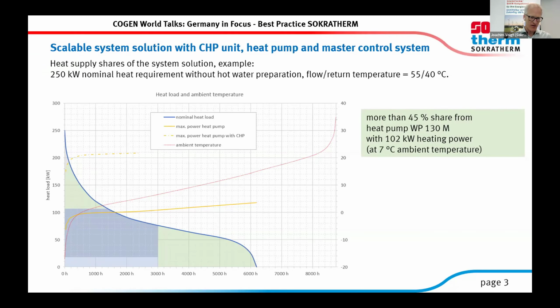As you see in the yellow curve, in the summertime, the heat pump is a bit too big, but this helps in the wintertime to cover more of the peak load demand with a heat pump, because it will be big enough to cover a huge share of peak load also in winter times. Of course, you are free to design the heat pump a little smaller than shown in this picture. The scaling of the heat pump in this example comes also from German policy guidelines.